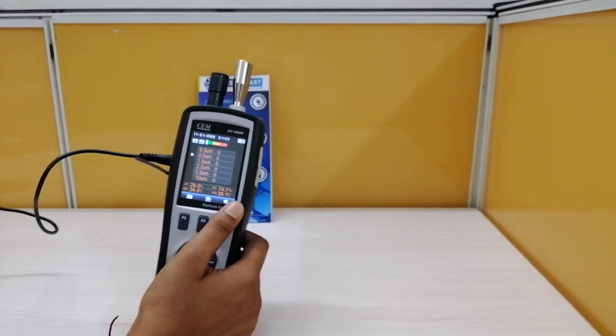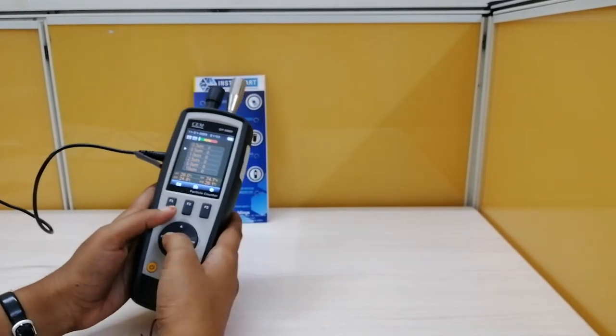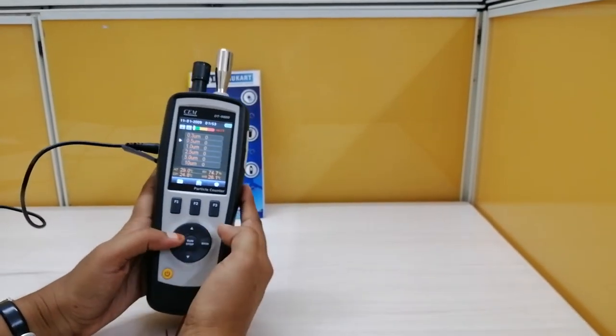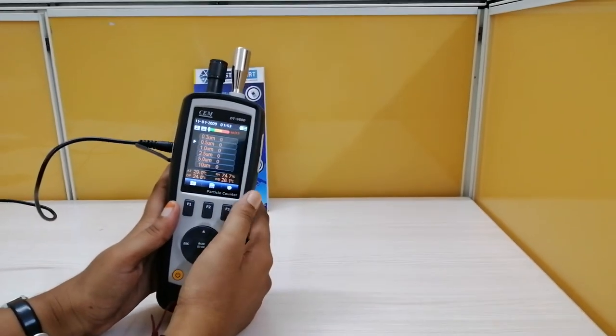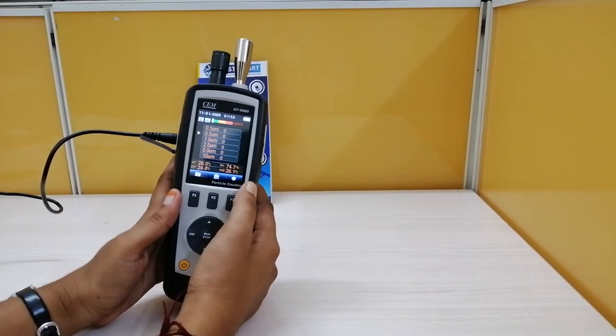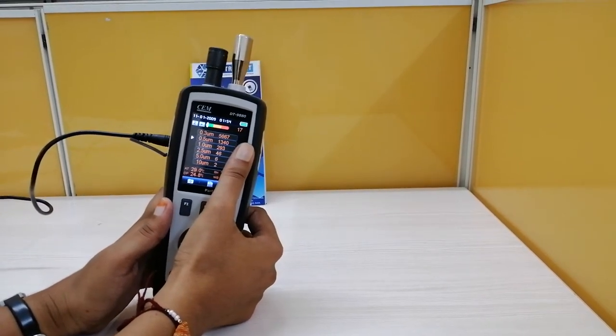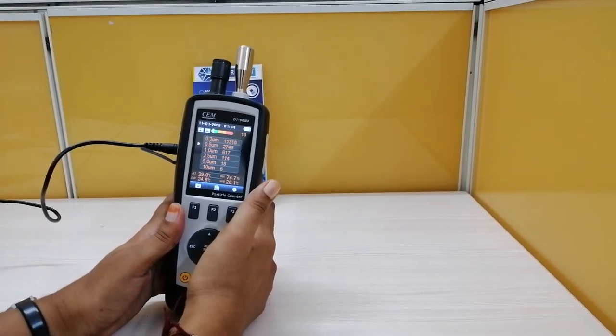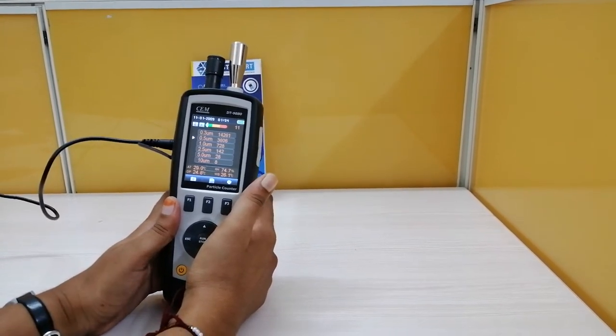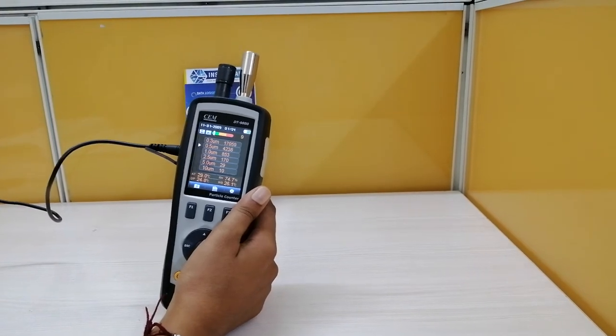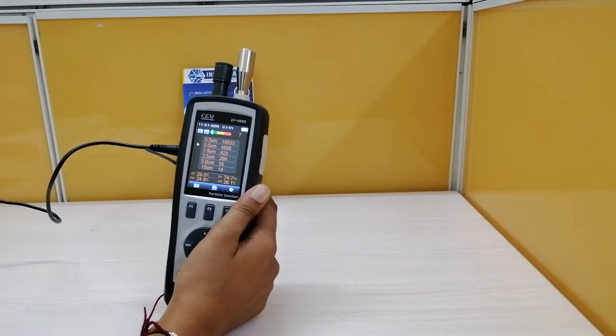Let's say first I will run the device. It is sampling. I have set for 21 seconds of sampling time. You can set a sampling time of maximum 60 seconds and flow rate of maximum 2.83 liters per minute.